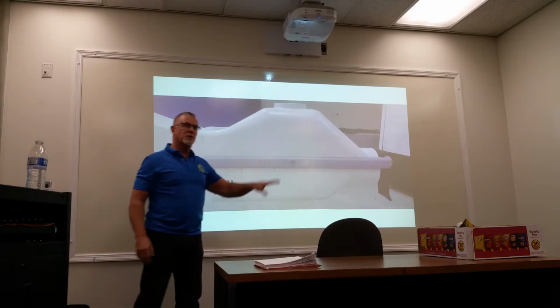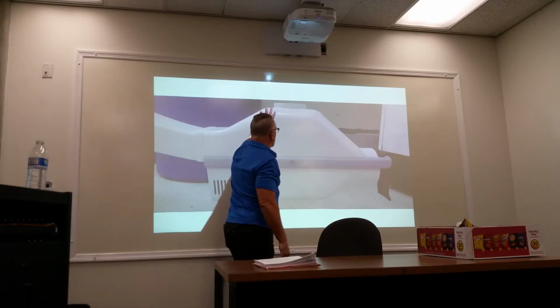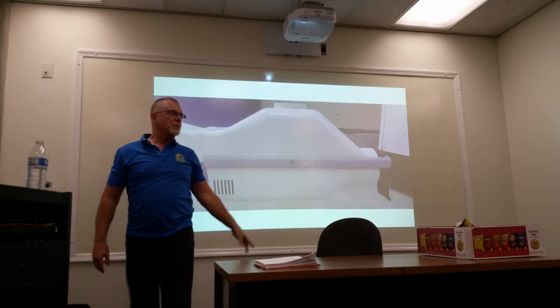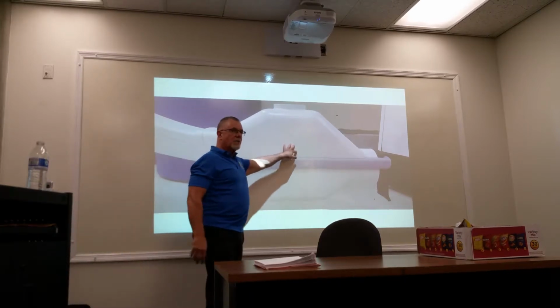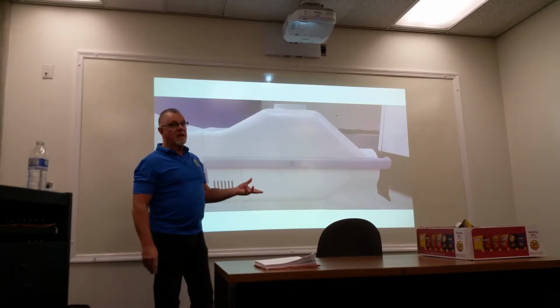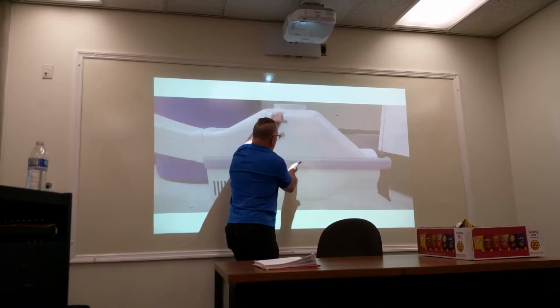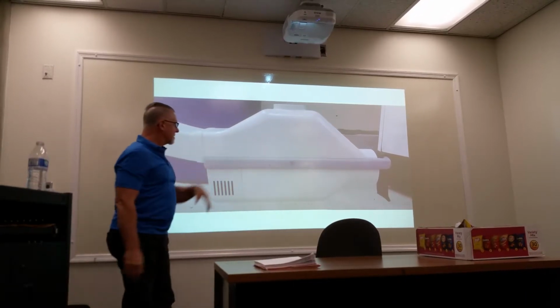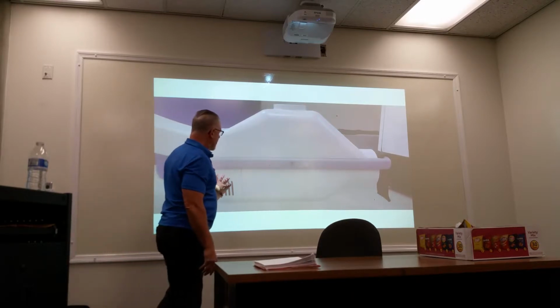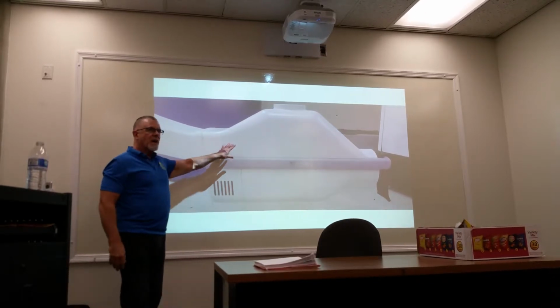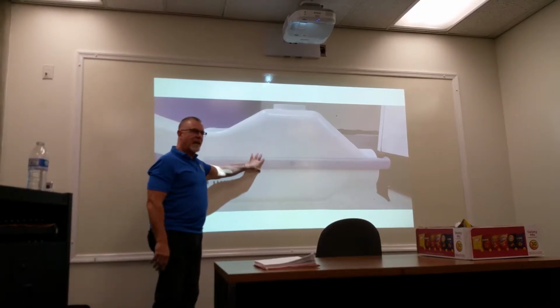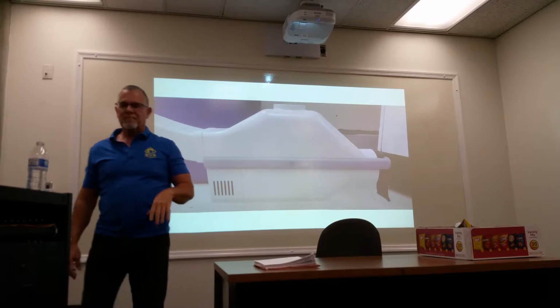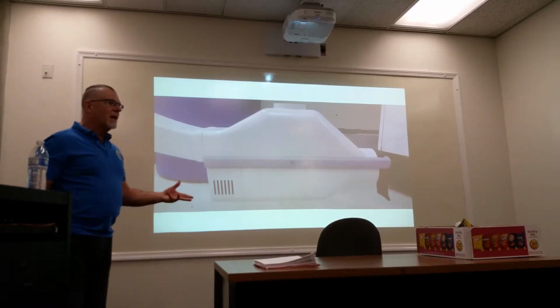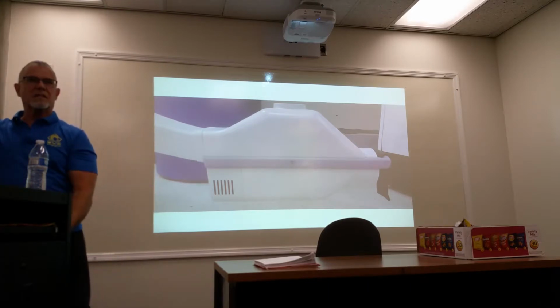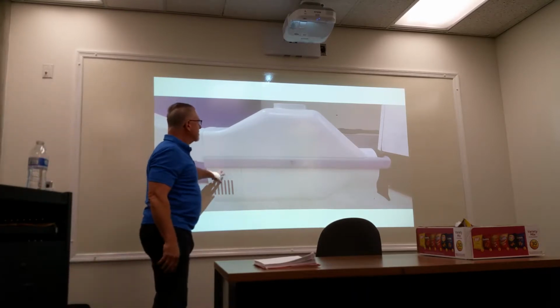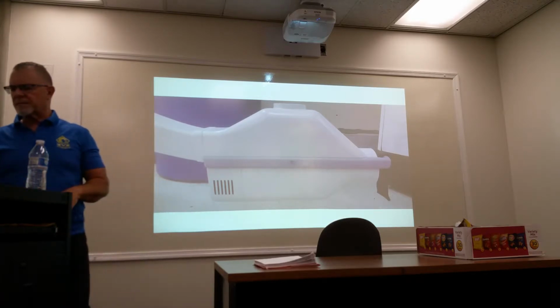Now this is a special tube. This is made for a surgical C-arm. There is no extension cone, so this can only be used in surgery. If you try to use this somewhere other than surgery, that's a problem. It's violating the law. This is set up to be really, really small, so you can fit under those surgical tables. You've got a vent here. Some of these units have the high tension transformer actually in the head of the tube. These things are getting really, really small. I'm used to high voltage equipment that's probably this size, and they've really gotten down. High frequency transformers are very, very small, about the size of a shoebox.